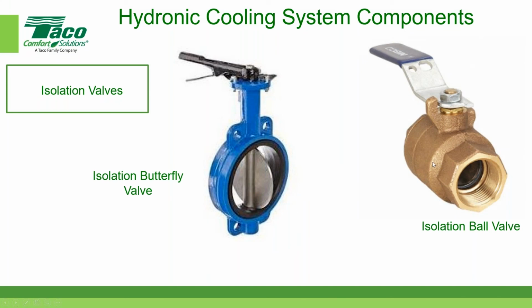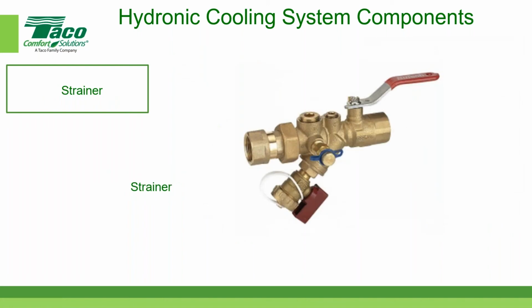We also have isolation valves. Now, Taco doesn't manufacture isolation valves, but there's a variety of companies that provide them. And probably for 2 inch and less, the typical isolation valve for HVAC systems is a ball valve. And for anything over 2 inch is probably going to be a butterfly valve. So those are the two most common types of isolation valves you find in a system.